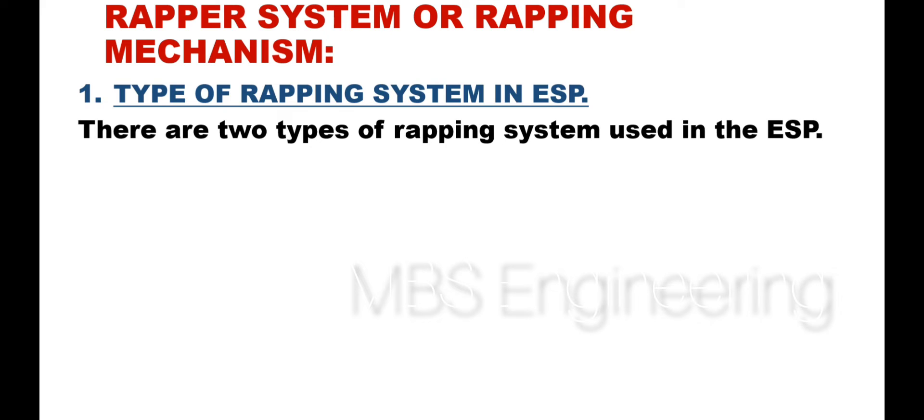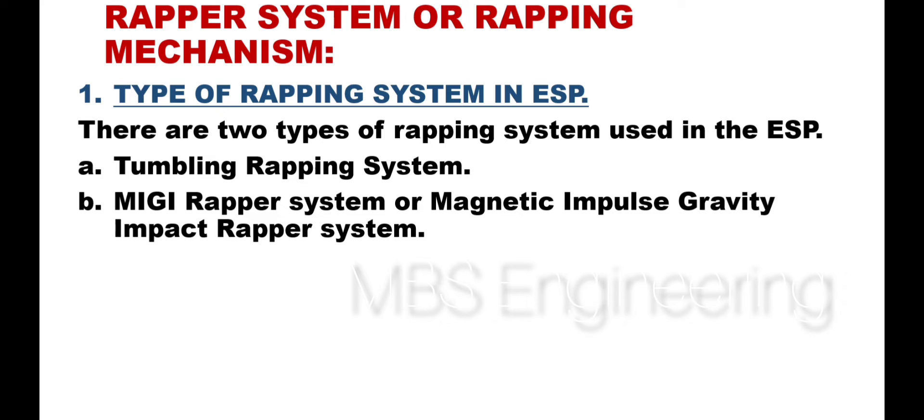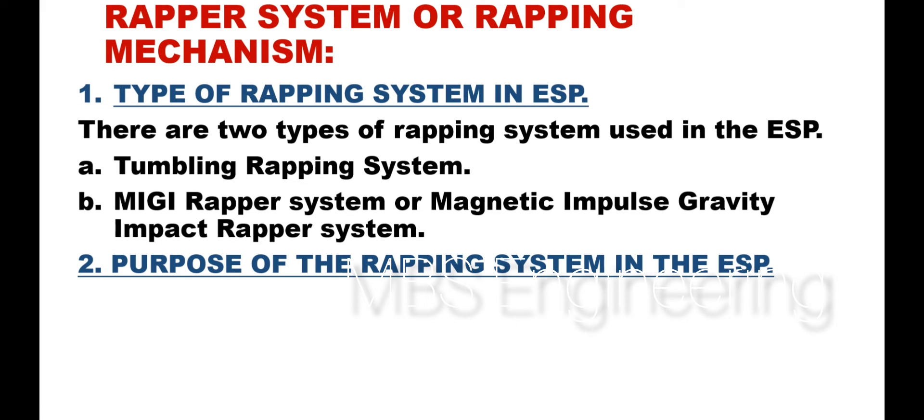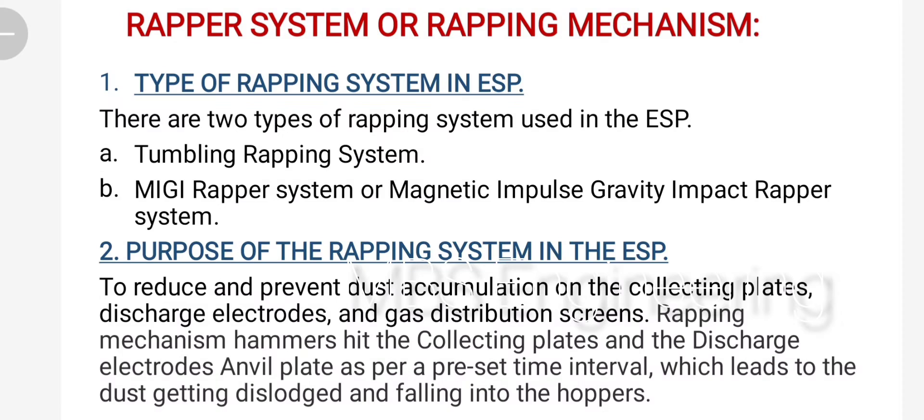There are two types of rapping systems used in the ESP. Point A: Tumbling rapping system. Point B: MIGI rapper system, or magnetic impulse gravity impact rapper system. The purpose of the rapping system in the ESP is to reduce and prevent dust accumulation on the collecting plates, discharge electrodes, and gas distribution screens. The rapping mechanism hammers hit the collecting plates and the discharge electrodes anvil plate as per a preset time interval, which leads to the dust getting dislodged and falling into the hoppers.